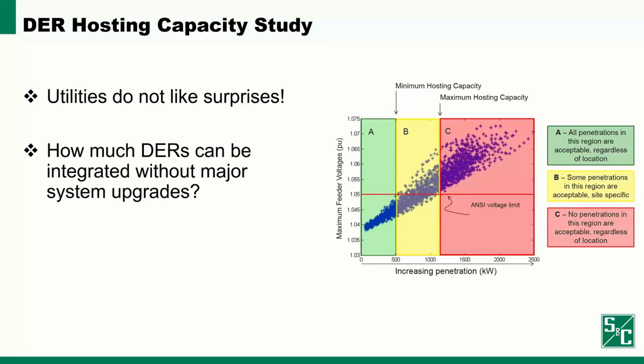In this example feeder, the probabilistic approach keeps adding photovoltaic generation sources at different sizes and locations into the system and keeps evaluating the voltage profile across the feeder. In this example, this designated feeder can accommodate up to 500 kilowatts of PV without any voltage problems, and even up to about 1100 kilowatts at certain locations. A similar study will also be performed for evaluating thermal limits of the equipment on this feeder as well. This study specifically was done using the software named Synergi, but there are other commercial software tools, such as CYME, OpenDSS, and Siemens PSS, among a few others, that can also be used for performing this analysis.